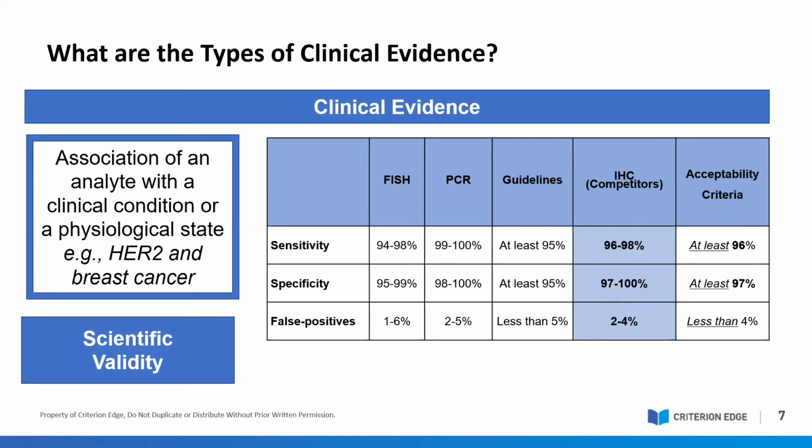So how do you define success? Are you using it to diagnose a clinical condition? In order to show that your IVD performs as intended, you must show that it has sufficient sensitivity and specificity compared to your nearest competitors. That's how you will ultimately set the bar. And that's the purpose of the SVR that we described in the previous webinars. It's to establish your competitive landscape by showing how your closest competitors perform.